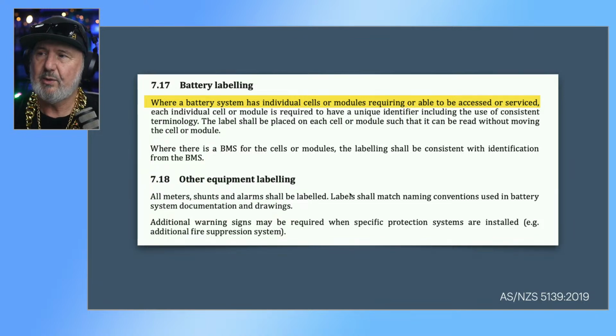In terms of other equipment, things like meters, shunts and alarms shall be labelled. For instance, if you've got an energy meter in a switchboard, there should be some indication of what that metering is for. And it's really important that labels match all the documentation. So if you're using words like DC isolator and DC switch interchangeably, they're not the same. This system is going to be often operated by someone who's not trained in electrical language, and they want to just be able to look for something that's called a DC isolator, and the label should say that. Equally, if your shutdown procedure lists shutting down the inverter by turning off the main switch inverter, make sure that that's what the label is on the main switch, not something different.